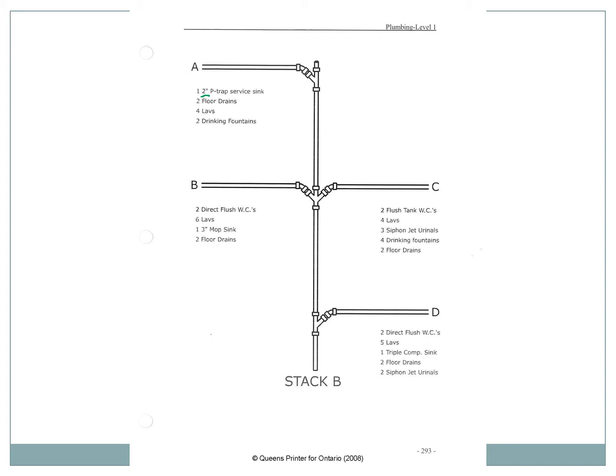You've got two options. A just says domestic sink or household sink, and it's 1.5 fixture outlet pipe with 1.5 fixture units. And that's not it, because we've been told it's 2-inch. So take a look at 23B. It says other sinks, and it gives us 1.5 inch is the minimum size. But then when you come over to the final column, the fixture unit column, it says simply 1.5 fixture units with a 1.5-inch trap, or 2 fixture units with a 2-inch trap. So that's what we have here, 2-inch trap, right? So that's the one we're going to use. We know it's 2-inch. We only have one of them. So that is 2 FUs.